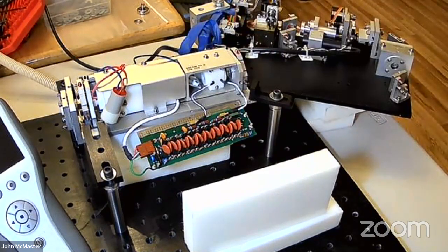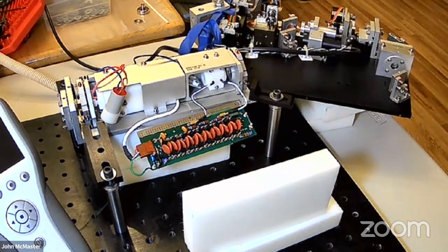And we have the quarter wave plate installed, which is rotating the polarization, but they're set up right now so they essentially cancel out. So the last thing we need to do is rotate this, it's like 45 or 90 degrees, I don't remember off the top of my head. Basically, you rotate it so that this will actually block the light initially because it will be the wrong polarization. But then this optical cell will rotate the light, and due to that rotation being lined up with this quarter wave plate, it'll suddenly switch the light when the laser fires. And you'll get one high power pulse coming out of the laser. At that point, the laser is at its full power once you've done a little bit more tuning. But you have all the components back in. It's firing a very short high power pulse. And that's how we brought back the other laser from the dead.